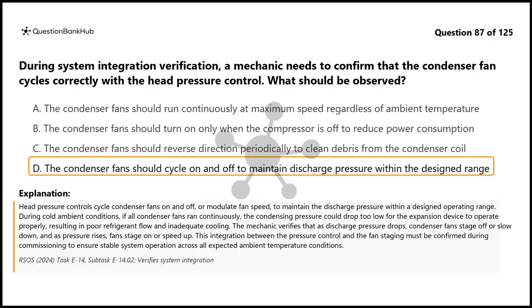The mechanic verifies that as discharge pressure drops, condenser fans stage off or slow down, and as pressure rises, fans stage on or speed up. This integration between the pressure control and the fan staging must be confirmed during commissioning to ensure stable system operation across all expected ambient temperature conditions.